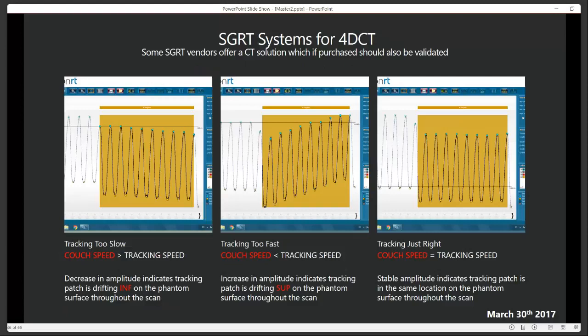The reason is the amplitude towards the inferior portion of the phantom is low. The amplitude towards the top of the phantom, the superior portion, is very high. And so if I put in a speed that's too slow to track, it will drop in amplitude. If I overcorrect, you see the second graph where the amplitude throughout the X-ray region, which is the yellow, is climbing, meaning the tracking is going superior along the patient. And then again, if I do it correctly and I put in the correct tracking speed for my CT protocol, everything stays at the same point, the amplitude stays the same, and I'm tracking the patient in the same location.